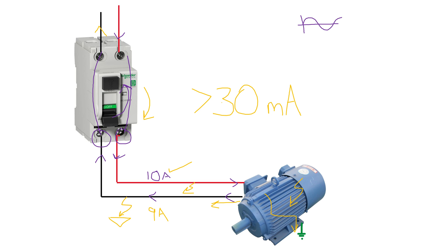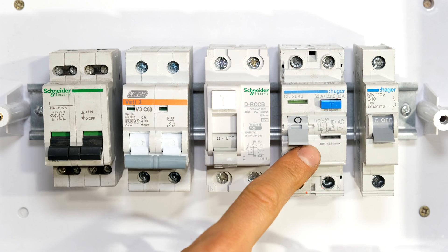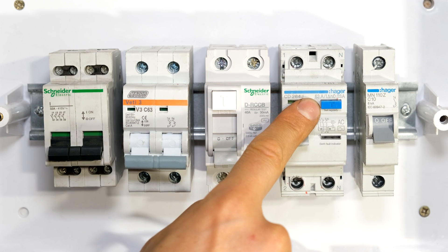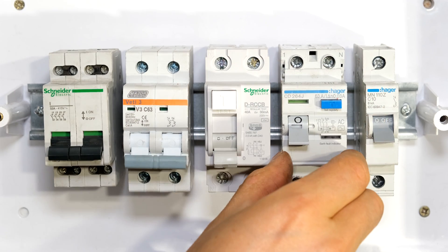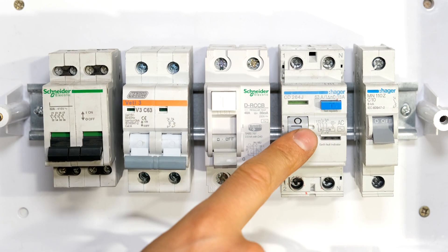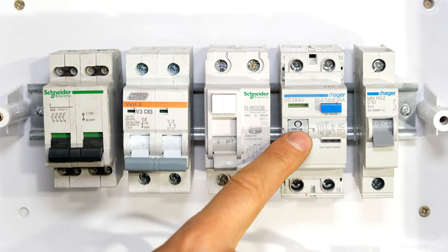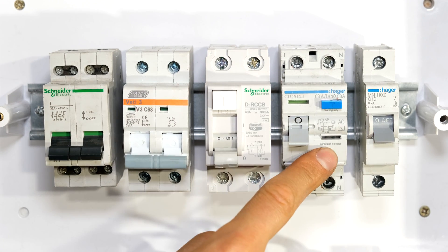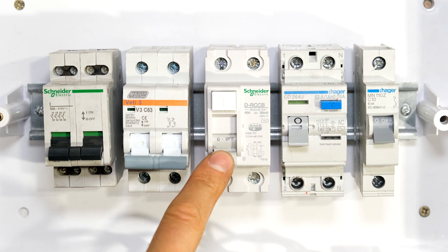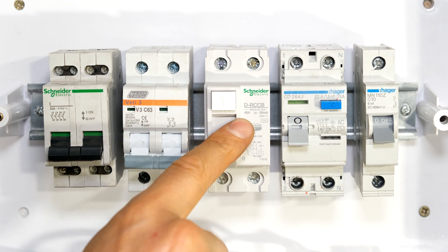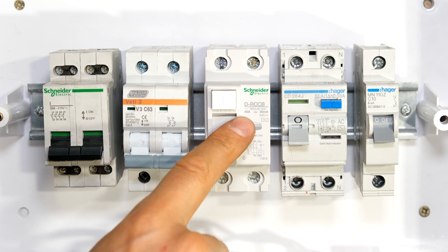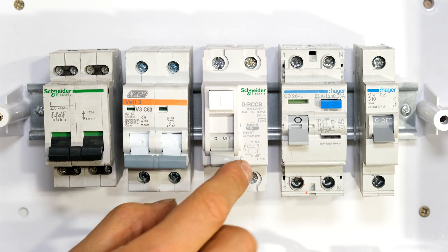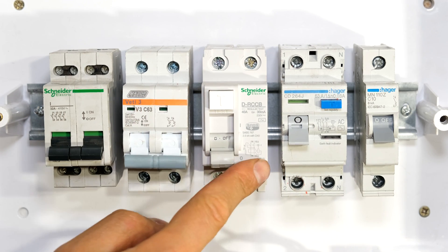30 milliamps is the maximum difference in current that the RCD should allow. What this particular one doesn't have is overcurrent protection. It can handle 63 amps traveling through the circuit breaker, but if you exceed that, you may damage the circuit breaker — it will not trip and will not open the circuit if there's an overload. This is only to measure the difference between live and neutral. The one to the left is the same, just rated at a lower current — 40 amps — so it can handle a 40 amp load, but this too will not trip if you exceed that current. It also works by measuring the difference between these two terminals.